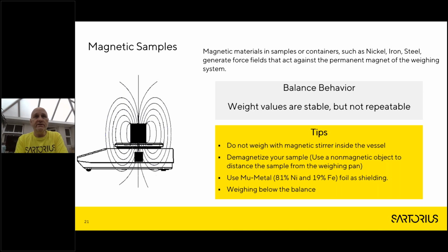So some tips here: do not weigh with a magnetic stirrer in the vessel. If you can, demagnetize your sample, or you could use mu metal, which is a shielding foil, on your balance pan to prevent any magnetic charge from getting through to the weighing cell. Or on many balances nowadays, there's the ability to weigh below the balance. So there's a small aperture underneath the balance where you can connect a hook directly to the weighing cell and you can weigh below the balance without any magnetic influence.